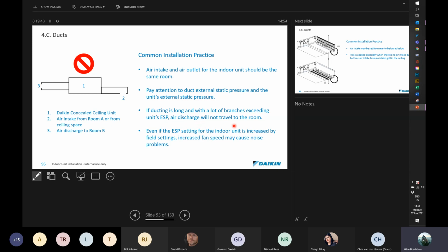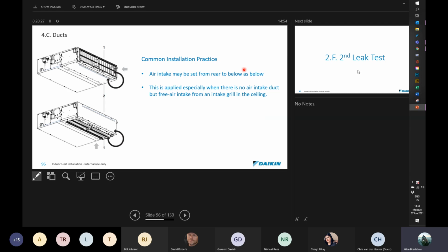If the ducting is too long with lots of branches exceeding the ESP, the air discharge will not travel to the room. So if you exceed the ESP, the unit is not going to supply sufficient air. And remembering that by increasing the ESP, you naturally are speeding up the fan, so you need to make note that that will also cause noise. When we talk about noise, it doesn't necessarily mean that it's going to be unbearable, but there is an increase in the sound. Depending on your application, that may be a bit of a problem if they're wanting a very, very quiet environment.